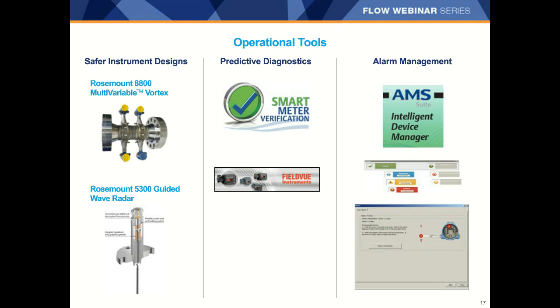The second layer is that of predictive diagnostics, or extra information from the instruments to the operators and technicians. Micro Motion Coriolis meters and Rosemount magnetic flow meters are both available with smart meter verification. This tool can be run in the background at configured intervals and is designed to check the health of the meter. This diagnostic tool can provide warnings of potential issues before the failure. For example, the smart meter verification on the Rosemount magnetic flow meter checks for all the critical components, including electrode circuit, coil circuit, and the electronics performance.